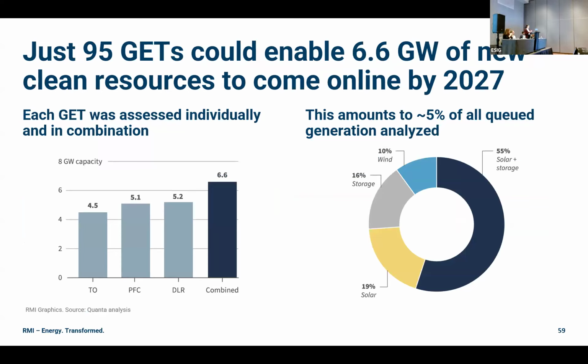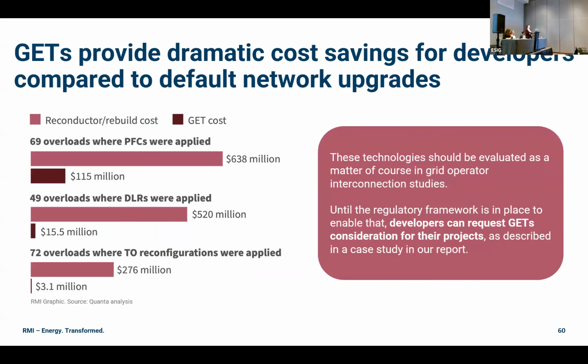And on this graph on the left, you'll see that we assessed each grid enhancing technology, both individually and in combination. So topology optimization, power flow controllers, and DLR, and then that combined bar is the 6.6. So in some cases, they cannibalize the ability of the other to address the same overload, and in other cases, they're very complementary. This amounts to about 5% of all queue generation, mostly solar and storage. Not only that, but these grid enhancing technologies are much cheaper, millions of dollars cheaper than the traditional or conventional network upgrade, which would be to reconductor or rebuild a transmission line.